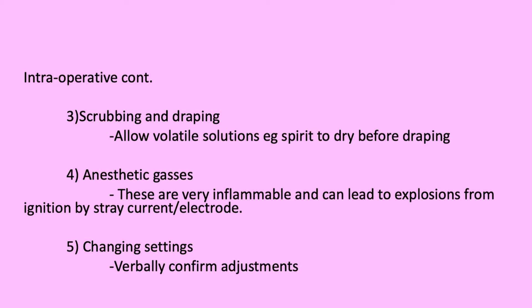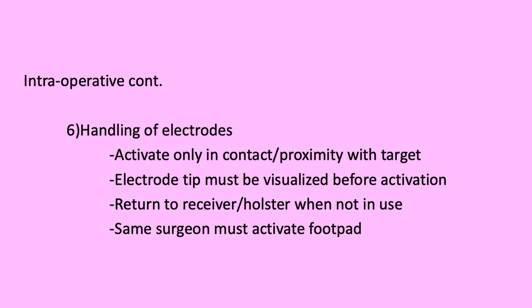When changing settings on the electrosurgical generator, this should be confirmed verbally to alert everyone. While handling the electrodes, they should only be activated when in contact with or in close proximity to the target tissue. The electrode tip must be visualized before activation and returned to the receiver or holster when not in use. The foot pad — which has both cut and coagulation buttons — should be activated by the same person using the pencil.